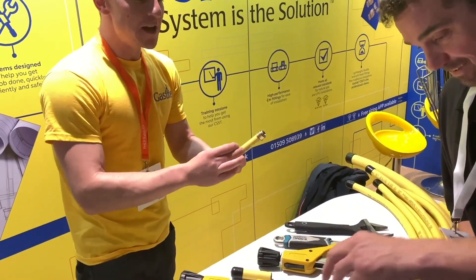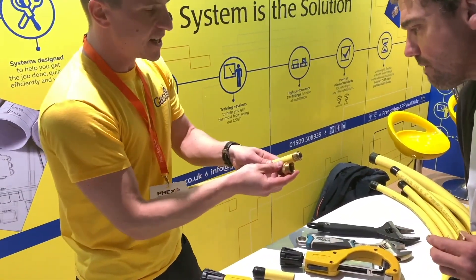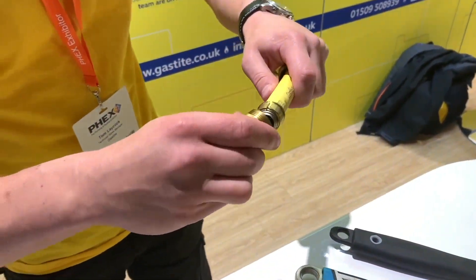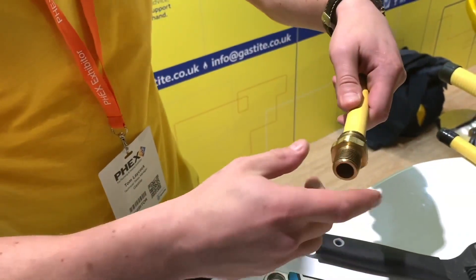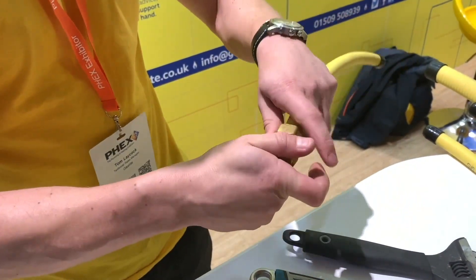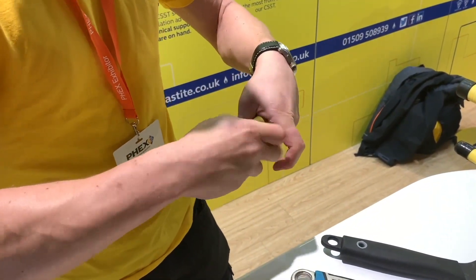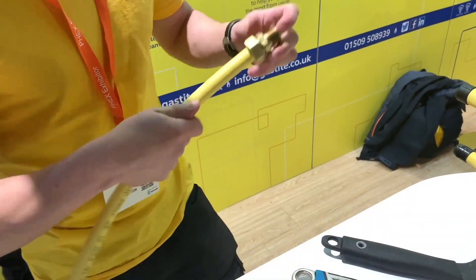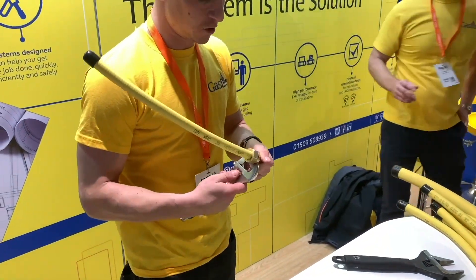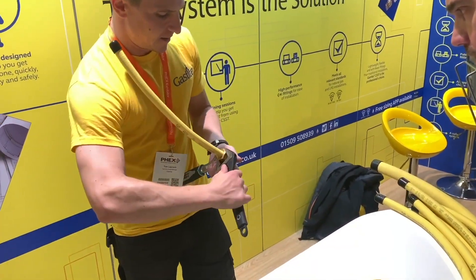Inside the Gastite fitting there's a centre insert, which is the source of the metal-to-metal mechanical seal. This guides over the top of those components, leaving a gap between the bottom of the fitting and the bottom of the bush. As you bring the nut up and torque it, that compresses the components into the fitting, creating a double seal.